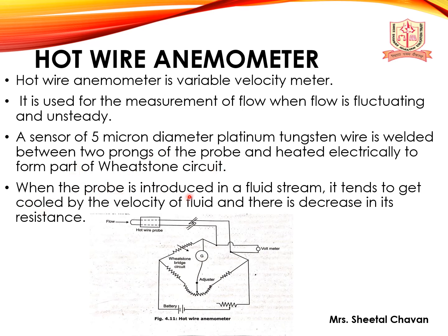When the probe is introduced in a fluid stream, it tends to get cooled by the velocity of the fluid, and there is a decrease in its resistance. So this is the diagram of a hot wire anemometer. This is the Wheatstone bridge circuit. This is the hot wire probe, and here is the fluid flow. And here is the circuit. Here is the battery, and this is the voltmeter.